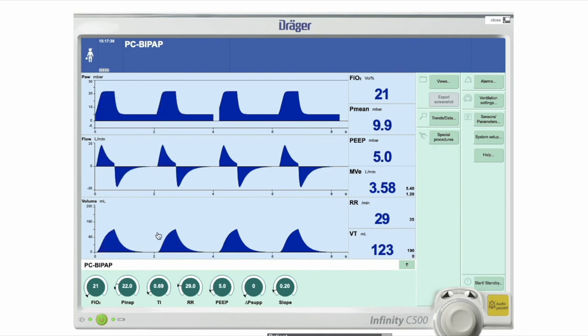So you can see you set 22 on 5. If you look at the pressure waveform, you can see it peaks at just over 20 and comes down to 5. So you're seeing that this patient is actually achieving the pressure that you're getting. Of the 3 waveforms, this is the most important. So this is the flow waveform, and you can get all sorts of diagnostic information on how the patient's being ventilated from this flow waveform. And we will be looking at that in a bit more detail again in a later video.